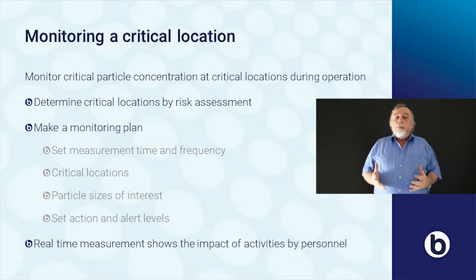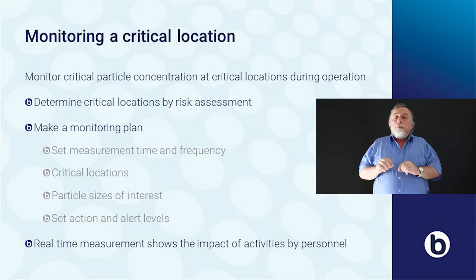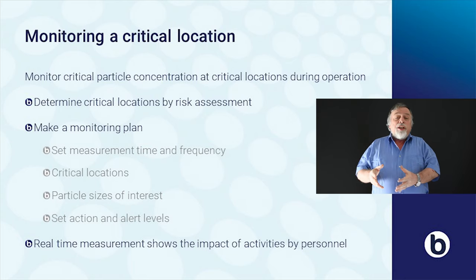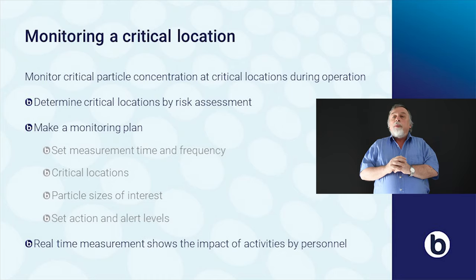A particle counter can also be used for monitoring. Monitoring is done at a critical location, measuring the particle concentration over time — continuously, each day, each week, or each month. How often and where you measure is determined by a risk assessment. You use the risk assessment to determine critical locations and critical moments, and that information is used to make a monitoring plan. In the monitoring plan you set measurement times, measurement frequencies, critical locations, particle sizes of interest, and you can set action and alert levels. With real-time measurement using a particle counter, you can directly observe the activity of personnel inside the clean room.